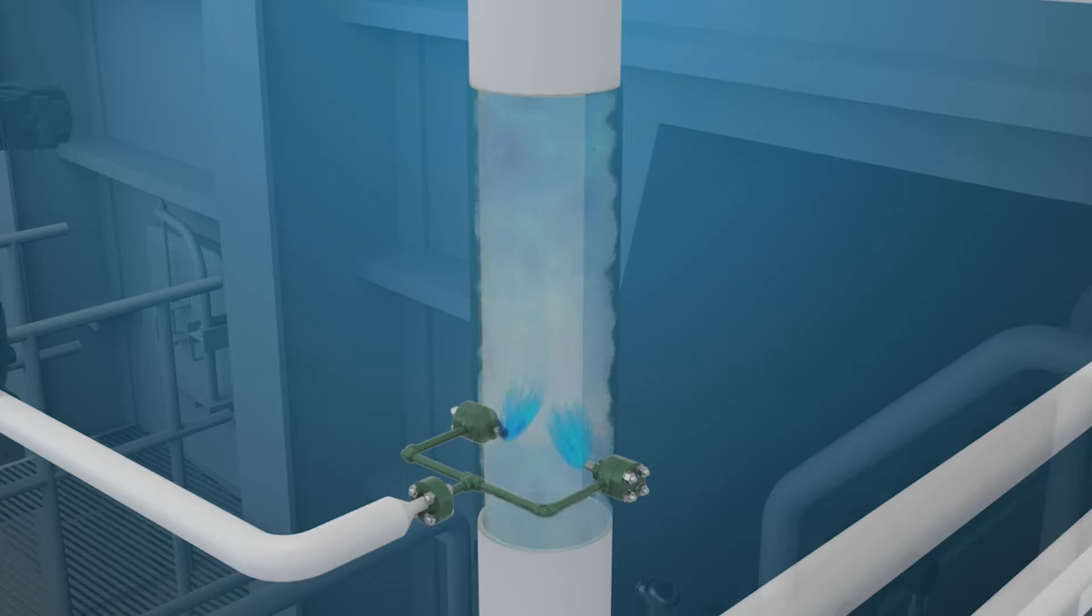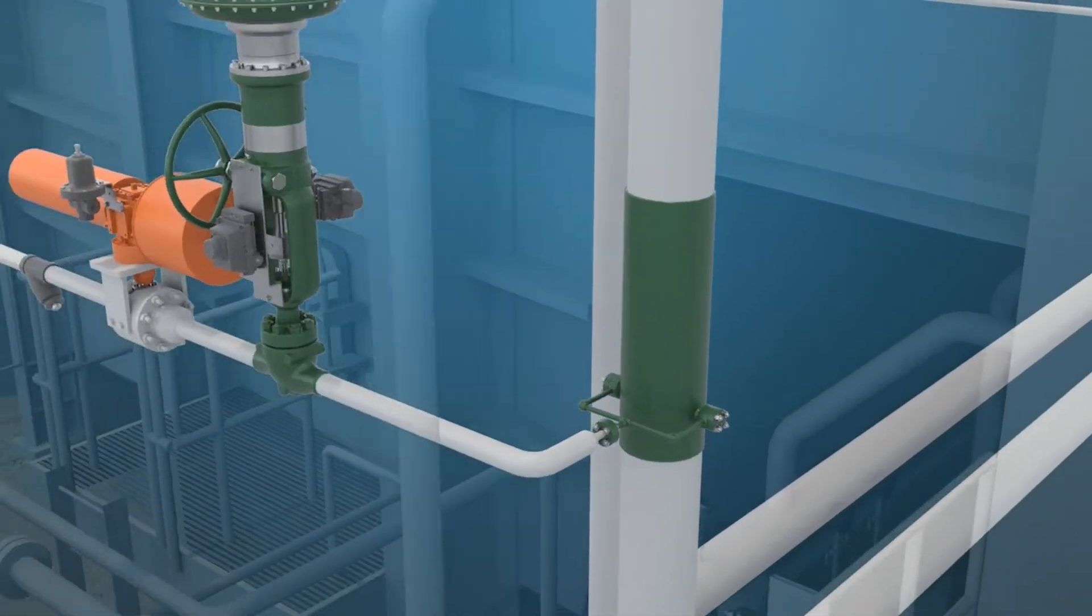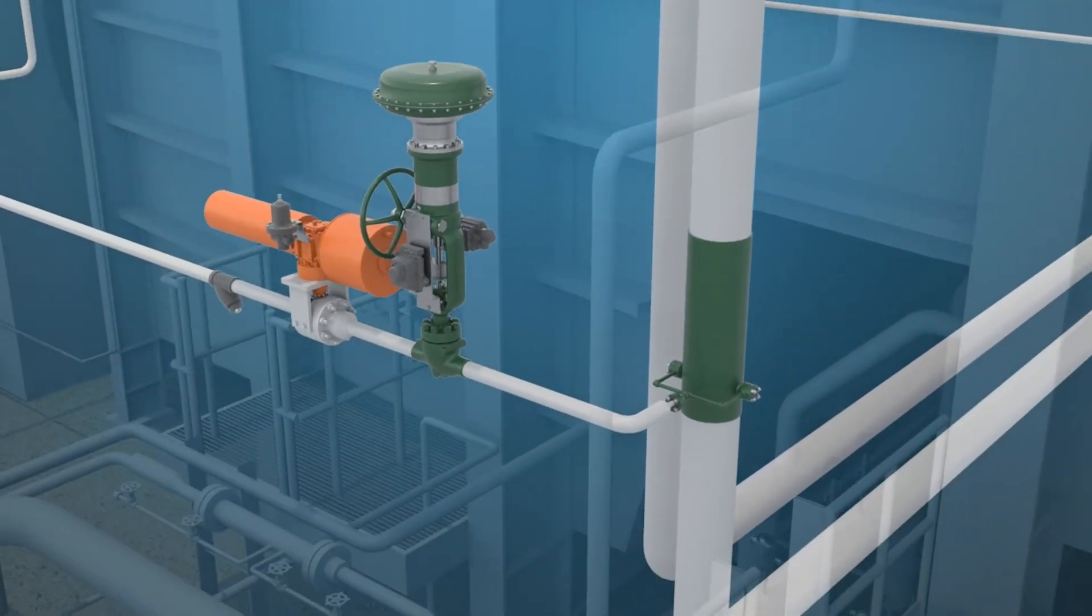The desuperheater can be a ring or insertion style depending upon the water flow requirements. The spring-loaded nozzles in the desuperheater have relatively small passages, and it is recommended that a strainer of suitable size for the nozzles be installed in the spray water line to prevent nozzle plugging.